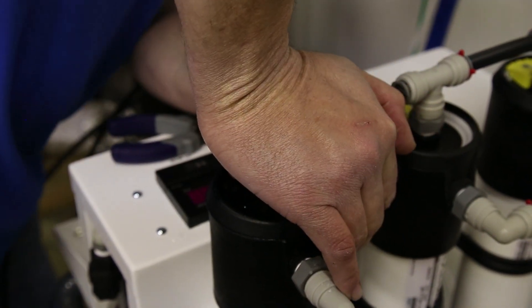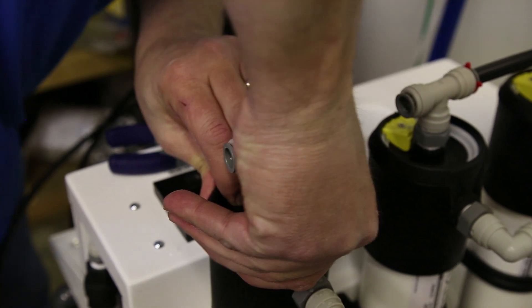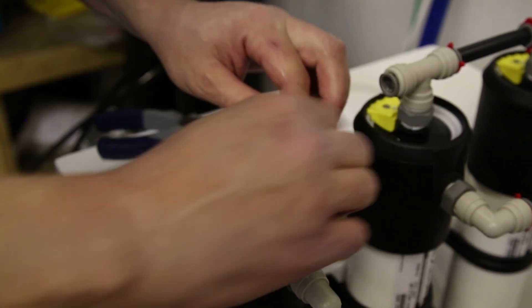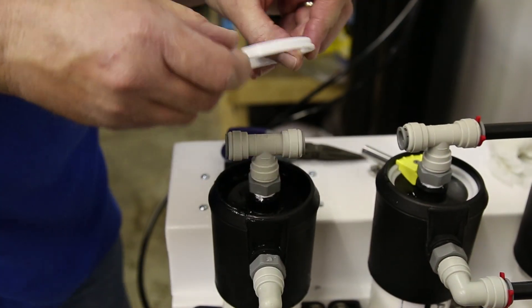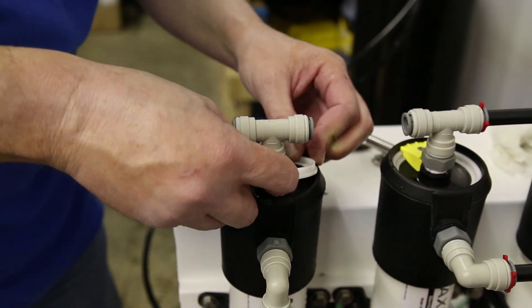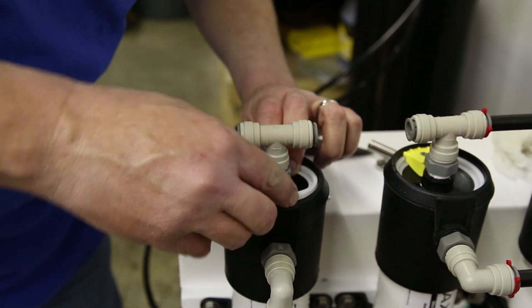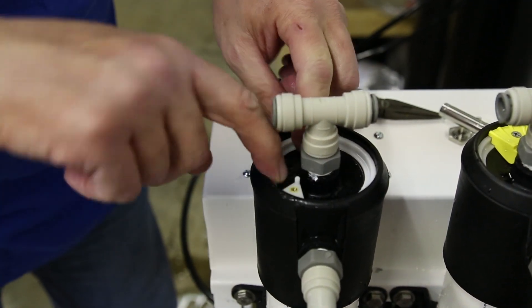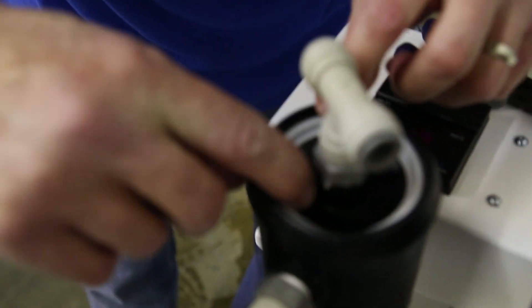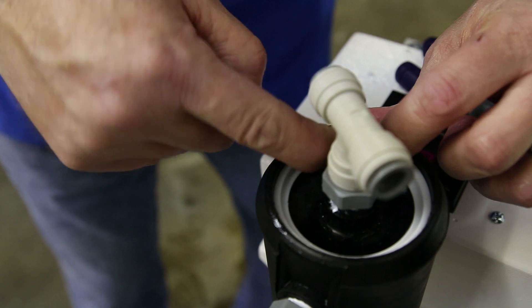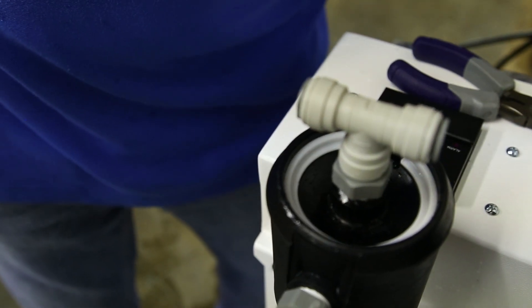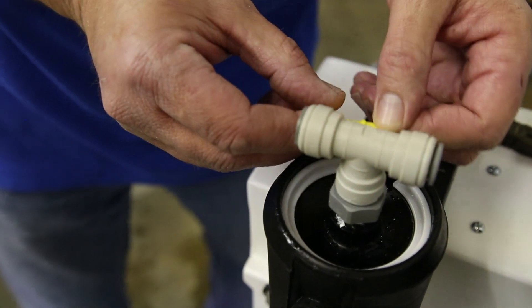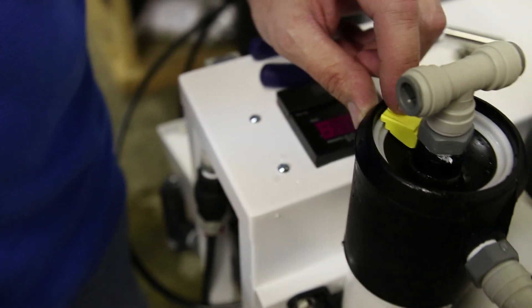I usually dry the water out of here. Then we're going to put the snap ring back in, putting the smaller end in first. Make sure it gets all the way in there and it'll snap in. You should have somewhat of a gap between here. If you don't, then it's probably not all the way in. If it's not all the way in and you start the system, it will pop out like a projectile.